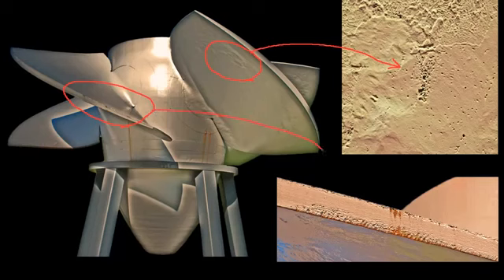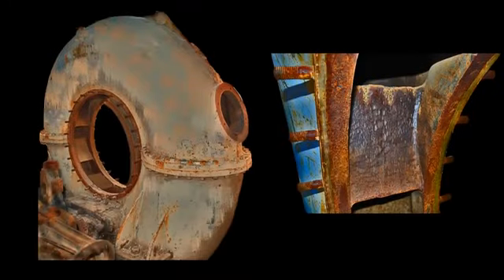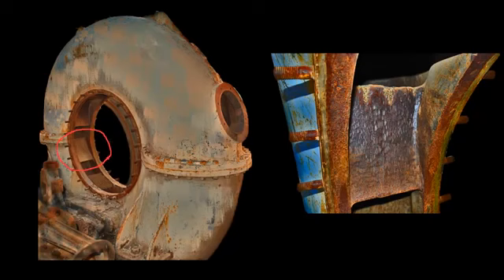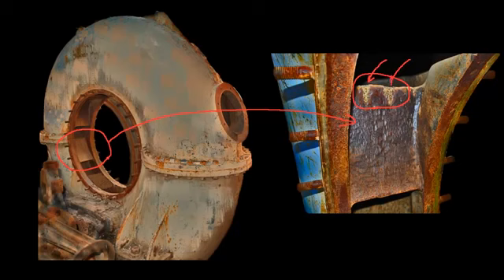Another example of cavitation is located in approximately this area of the blade tip of the turbine runner. This next example is also of a hydroelectric facility. This particular facility dates back to the early 1900s and is now abandoned. This is a picture of a horizontal turbine housing. If we look inside the housing, we can see the results of cavitation and erosion that occurred over the years of service. Also notice that you may be able to see what appears to be the results of a brazing process repair in a couple of locations that occurred sometime in the past.